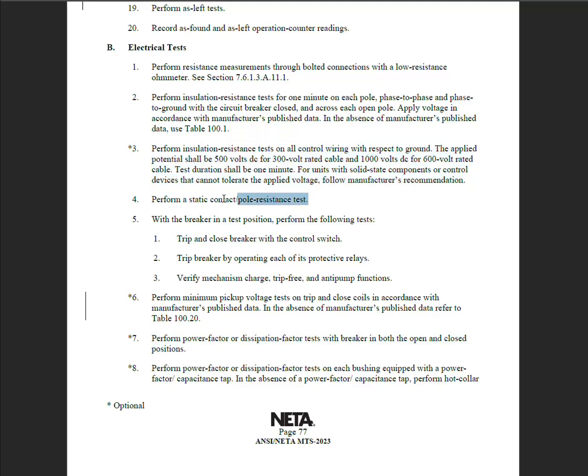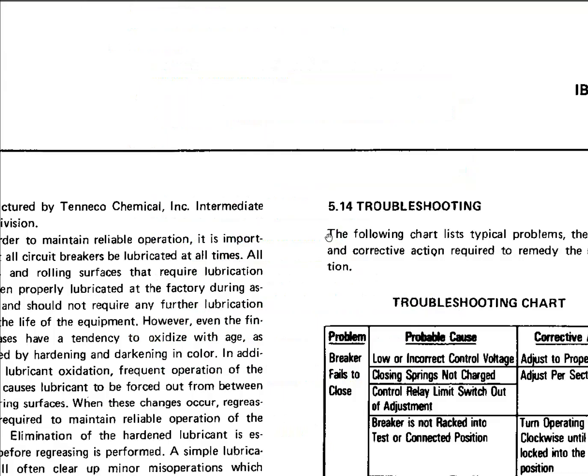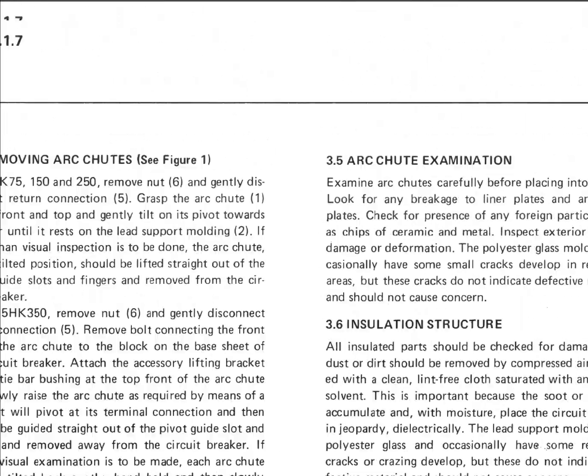Perform static pole resistance check, okay, but there's nothing specifically that says dielectric or high pot. And what you're going to find is a lot of these older manuals, it tells you that the insulation resistance is the dielectric resistance, okay? And so let's go ahead, let's go to this. This is the manual right here. I'm going to scroll up to the top so you can see.